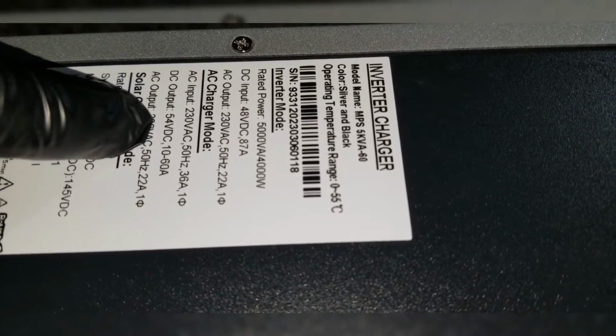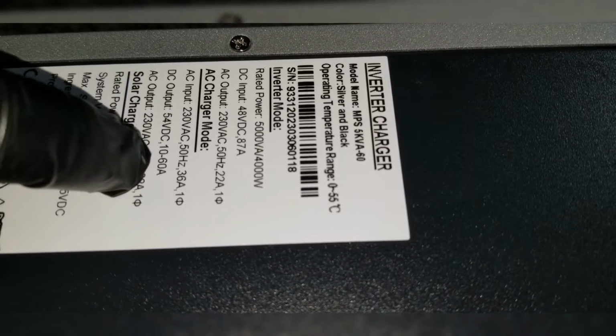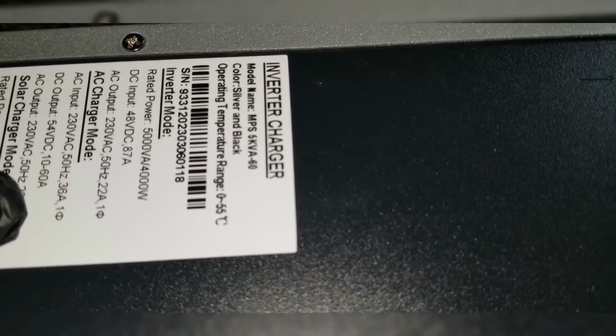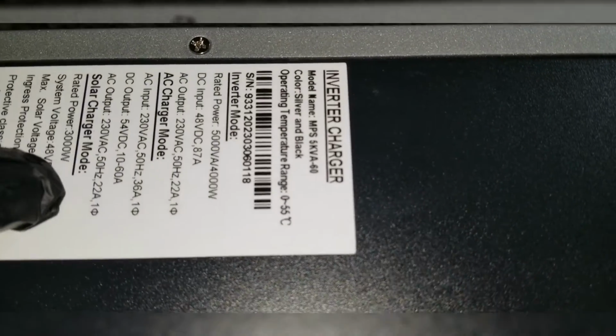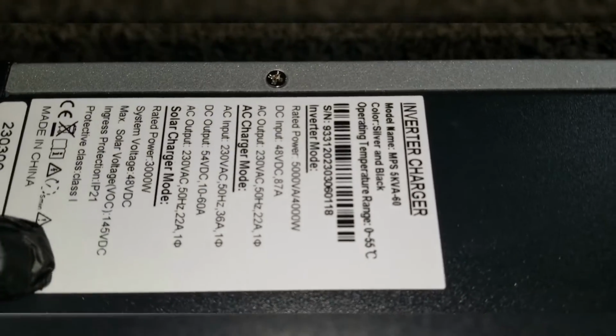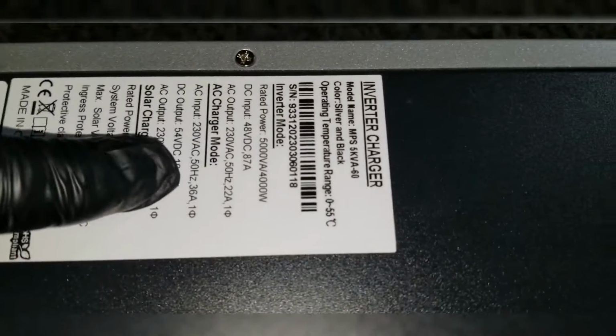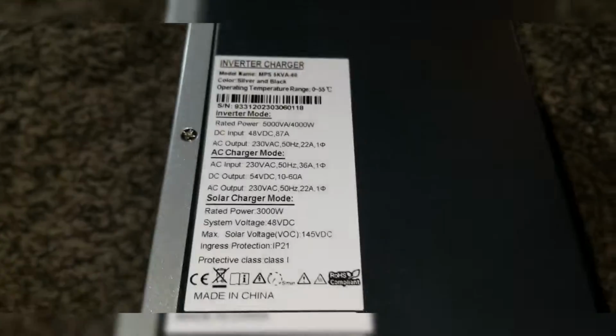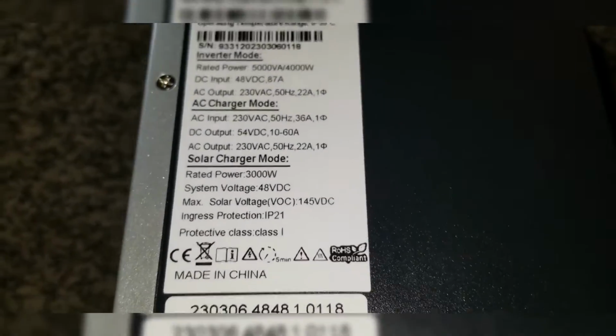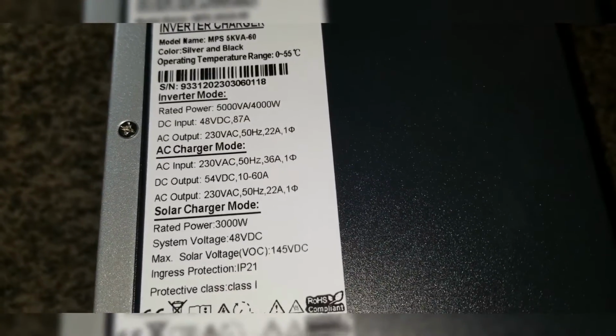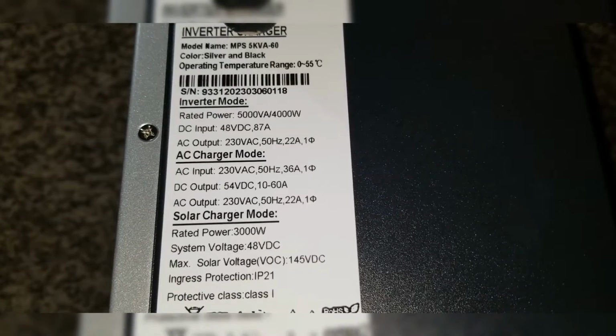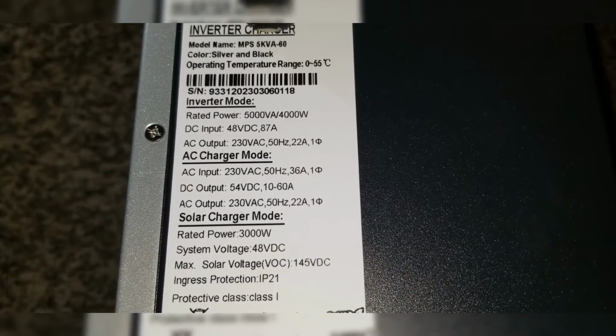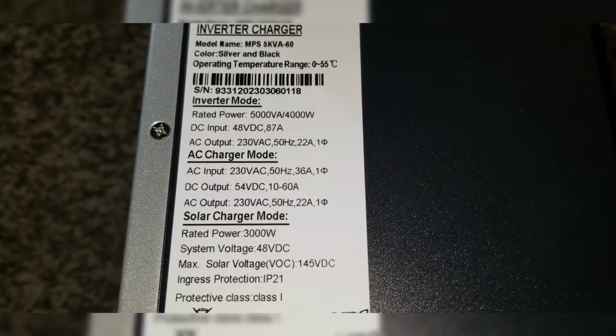The DC output is about 54 volts DC, and it can go from 10 to 60 amps. So there might be a 60 amp charge controller inside this unit. We'll have to check it out when we connect it and see exactly, because you can choose what amperage you want to charge your batteries. The model is an MPS 5kVA-60, because the 60 indicates a 60 amp charge controller built into this thing.